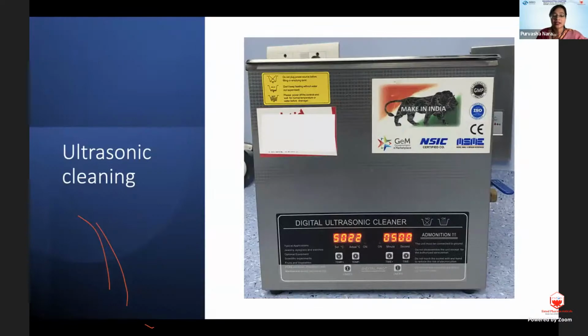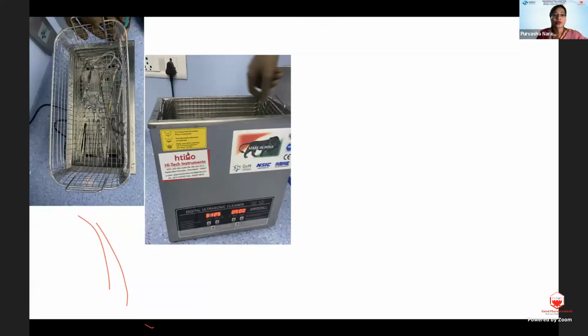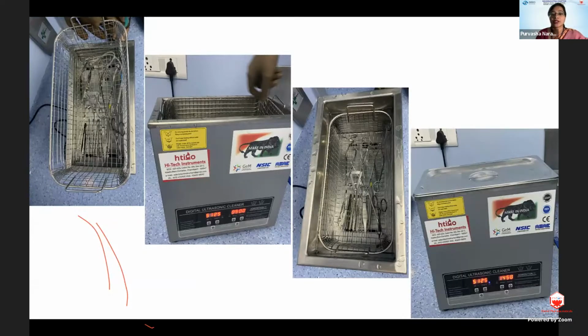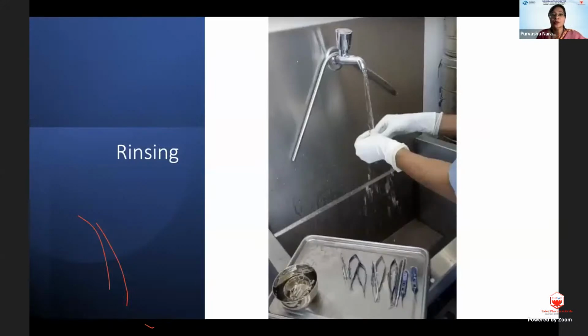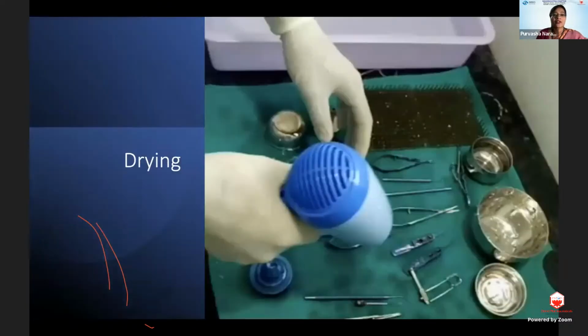If we have the ultrasound cleaner, like in our institute, we use that. The instruments are placed in the tray, lowered and immersed into the water in the ultrasound cleaner, and covered with a lid. This is run for a 15-minute cycle at 50 degrees centigrade. So this is the ultrasound cleaning of these microscopic instruments. After this, we need to rinse and flush again, because any debris or organic material which is dislodged should be rinsed off, and this is done using RO water. Then the instruments are placed in a clean tray, after which they can be placed on a clean cloth, and we usually use the hair dryer for drying. The bigger ones can be dried with a sterile cloth, but the tiny ones are dried better with hair dryers.